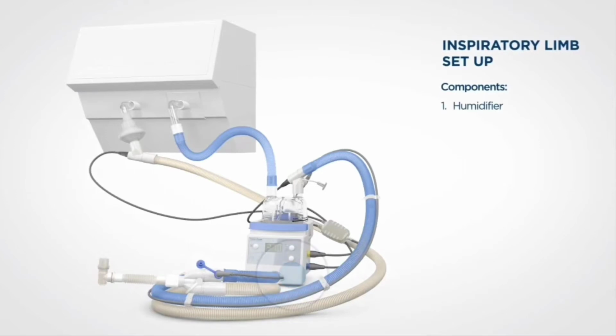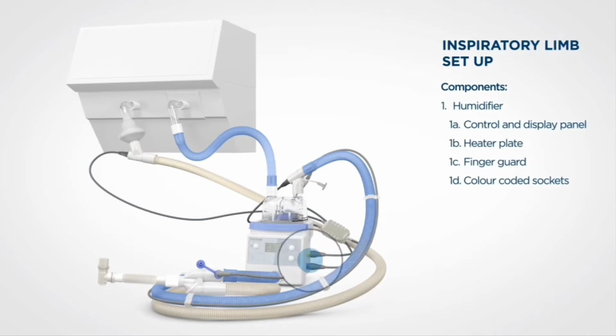This is the humidifier. It has a control and display panel at the front, a heater plate and finger guard on top, and color-coded sockets to connect electrical adapters and sensing probes on the side. This is the humidification chamber that holds water. It is filled from a rigid or flexible water bag through the water feed tube.